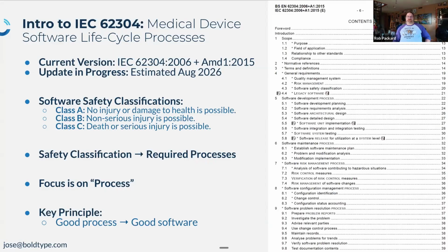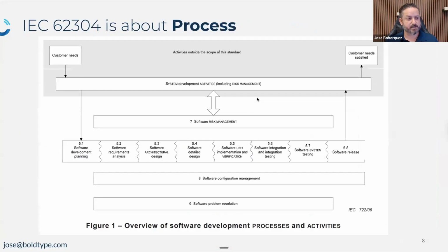What I really wish is that the FDA would come up with a little better guidance on how to migrate from what the standard says to what they're using, or just marry themselves to what the standard says. It seems like this is an opportunity, but that doesn't mean they'll agree with the new standard. Yeah, good point. The verdict is out because it's not out yet, but I can tell you it's not going to be a perfect match either. You have to perform the analysis from the FDA standpoint when it comes to enhanced versus basic. And as Rob has been saying, you want to do it early in the process because you don't want to have to go back and retrofit your design history file.